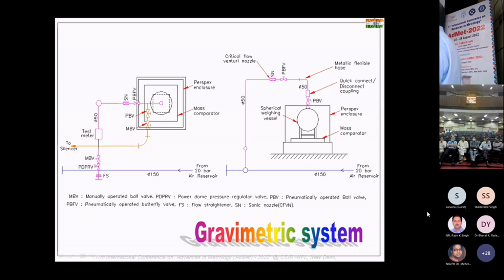So you have the mass, and the valve is connected with a timer, so you will get the mass flow rate. If you look at a 0.3%, 0.5% accuracy, this is good. But we are aiming at a much better tolerance.